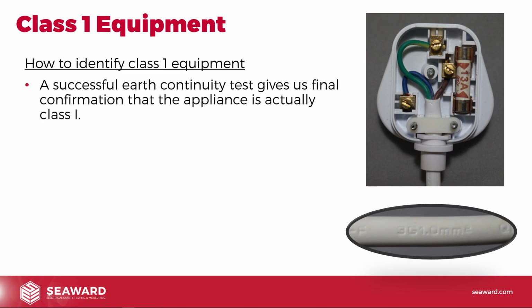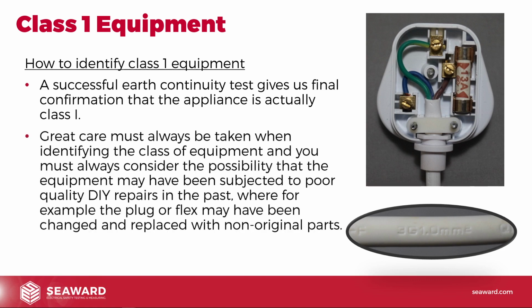Now, a successful earth continuity test gives us the final confirmation that the appliance is actually Class 1. So generally you'll assume it's Class 1, go ahead and do a Class 1 earth continuity test to earth metal parts, and obviously if it passes, then you're pretty convinced. Class 2 equipment won't have any earthing connection through to metal parts. So if you're getting earth continuity there, you're pretty convinced that you've identified that equipment correctly.